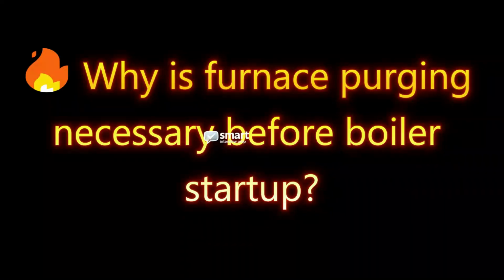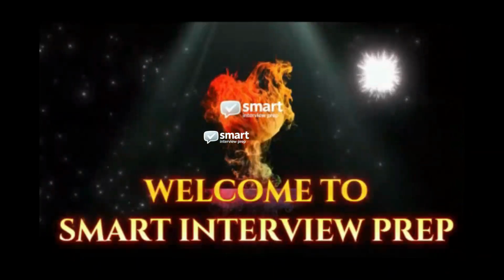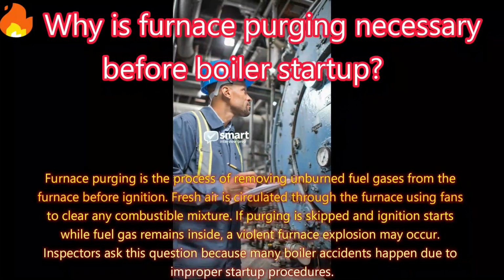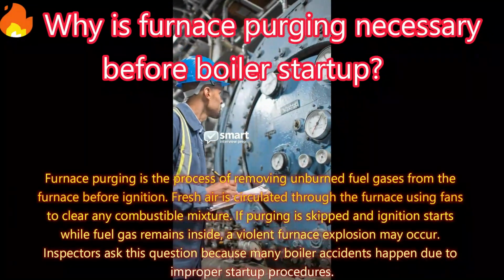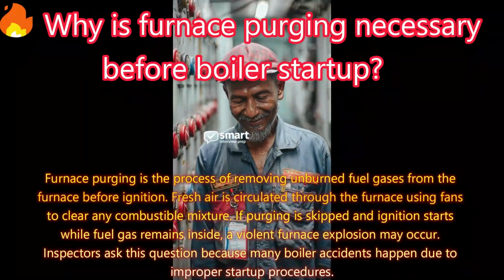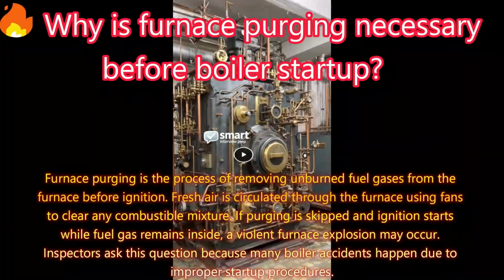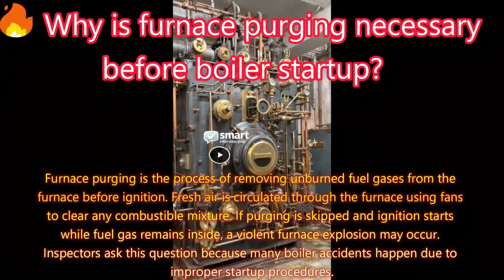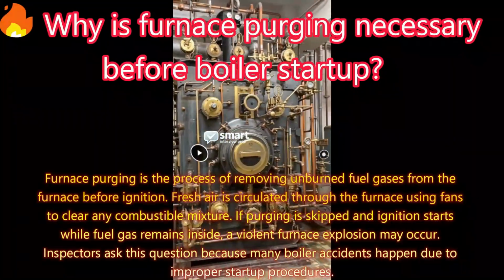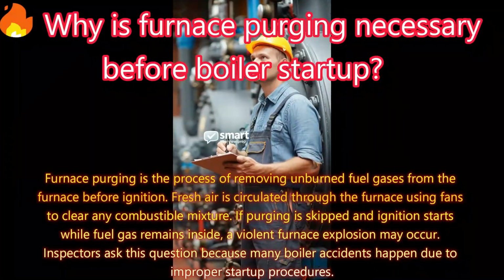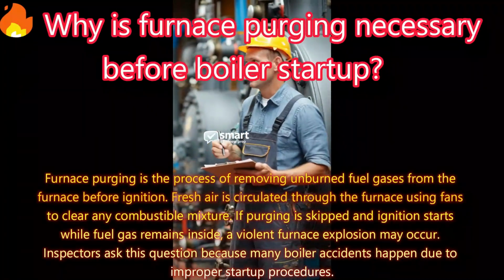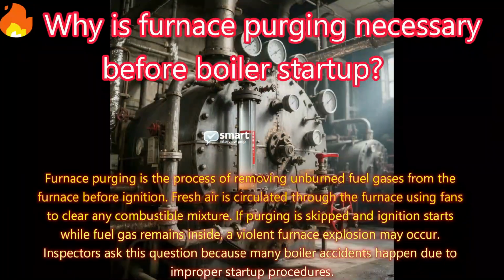Why is furnace purging necessary before boiler startup? Answer: furnace purging is the process of removing unburned fuel gases from the furnace before ignition. Fresh air is circulated through the furnace using fans to clear any combustible mixture. If purging is skipped and ignition starts while fuel gas remains inside, a violent furnace explosion may occur.